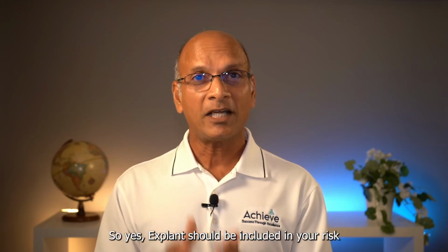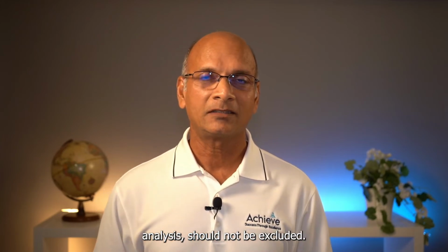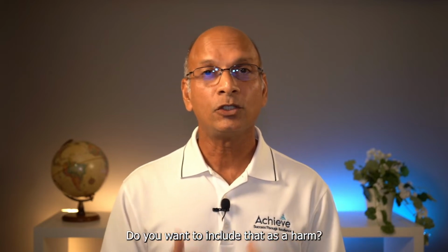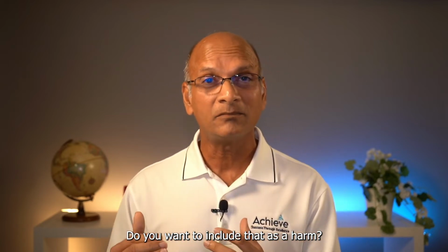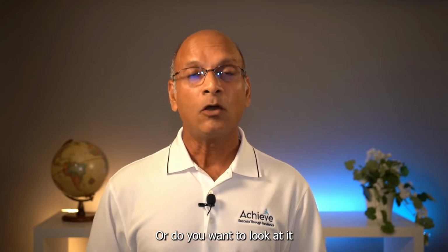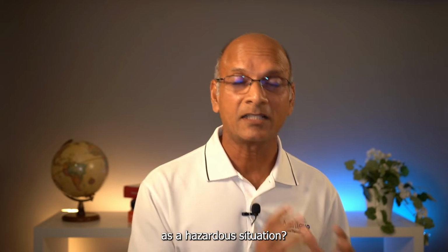So yes, explant should be included in your risk analysis, should not be excluded. But how? The question is how? Do you want to include that as a harm, which means that you have to assign it a severity level? Or do you want to look at it as a hazardous situation?